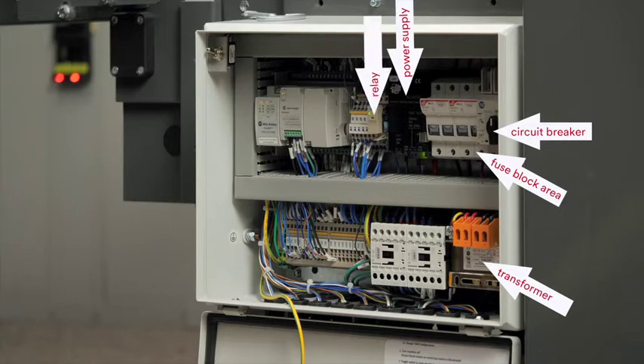There are 3 relays. One functions as a master control relay for removing power in the event of an e-stop and reapplying power once the e-stop is cleared and a reset is performed. A second relay acts as a motor contactor, applying AC power to the drive motors via the PLC. The third relay senses the low pressure switch and signals the PLC the pressure status.